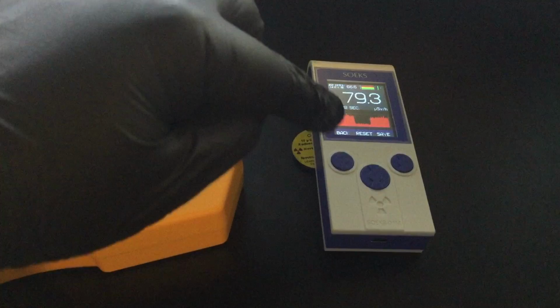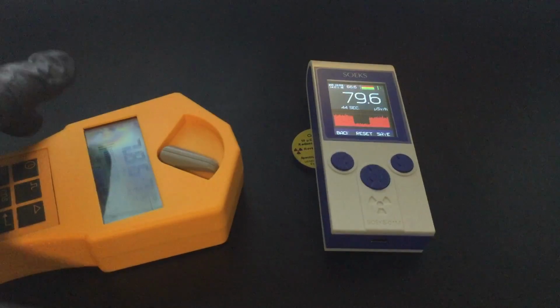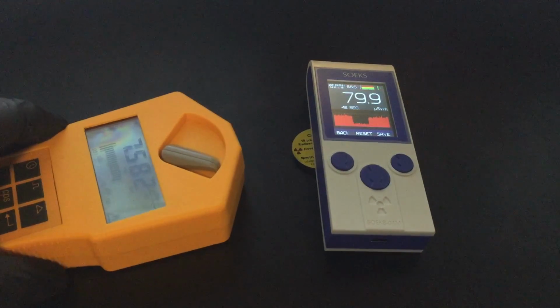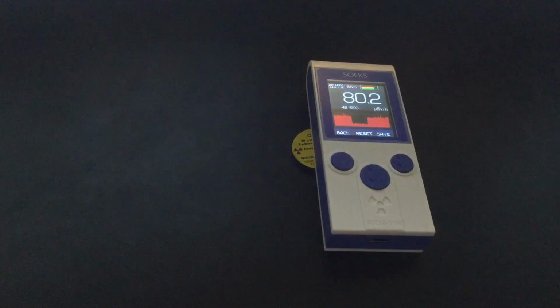And you can see the drop in the graph where I moved it off of it for a moment. So we may get up to 100 there. I'm going to move this to the side of the table, and it should calm down below alarm value. Yep, there it goes. Just a meter, probably 2 feet away, and it's showing 0.2 microsieverts right now. And I'll tap the button twice to reset it.